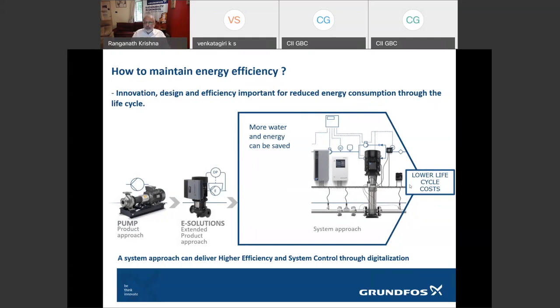The next step that you see in the box there, you have a complete IoT system with sensors all over and what we call adaptive technology, where the pump learns how you use it and what it needs to do to ensure that it is running at its most efficient point throughout its life cycle. And if there are any issues, they even give you a signal as to what is going wrong. So it's very vital to have a system approach to deliver higher efficiency and use IoT, use your startup systems, use all that you have today in terms of electronics and sensors to make sure that you have a system which is tuned to run at the highest efficiency and save you the largest quantum of power.